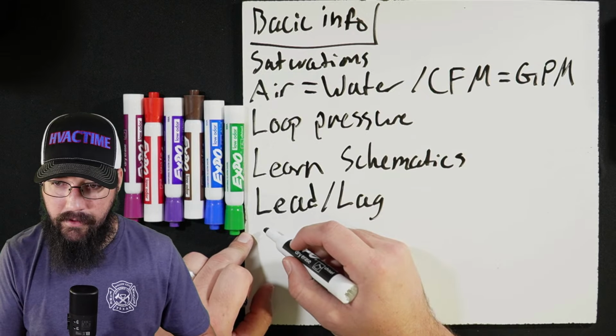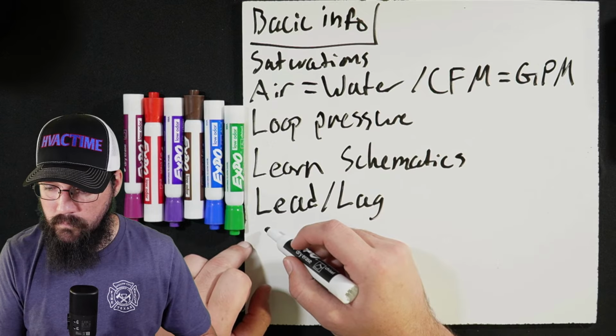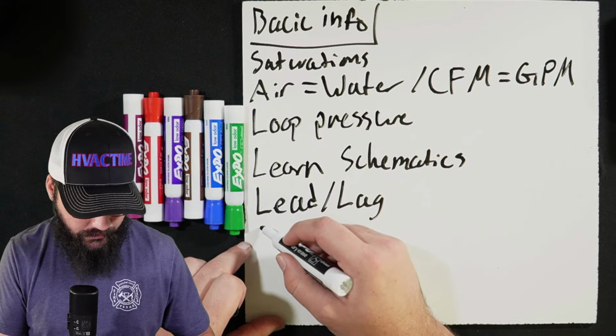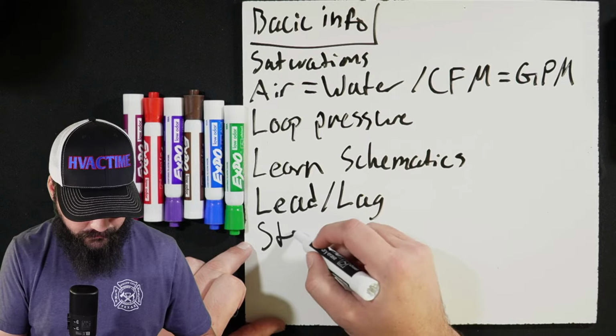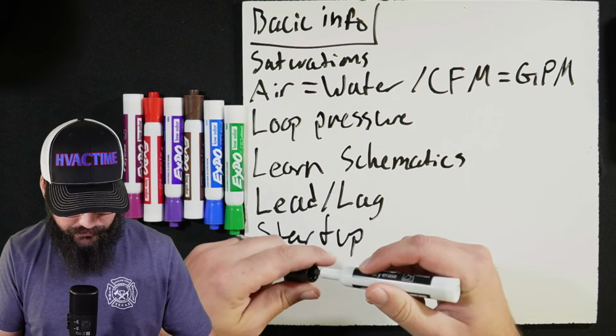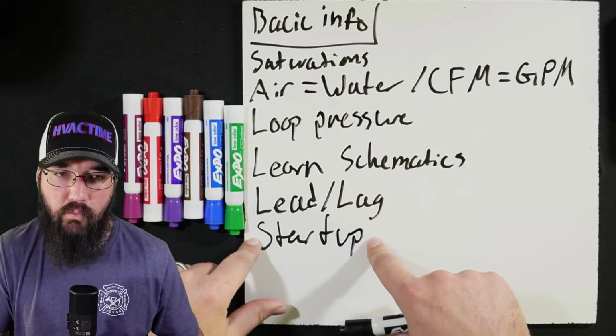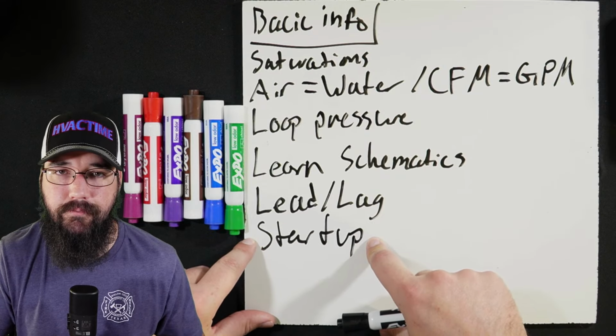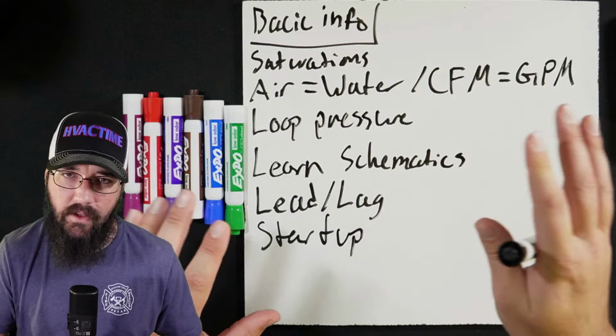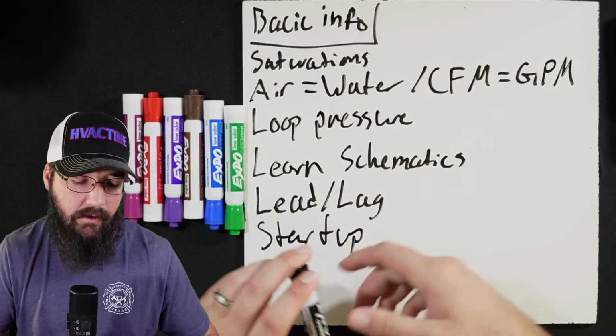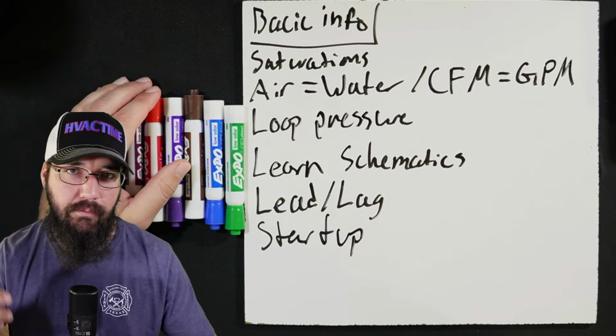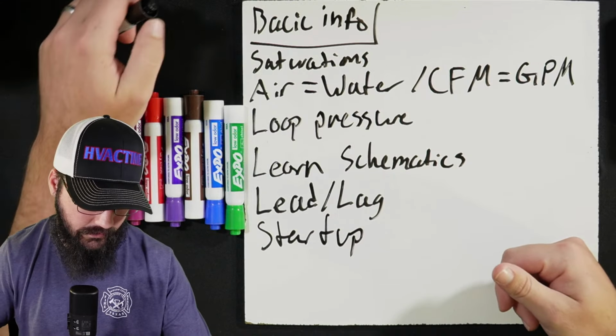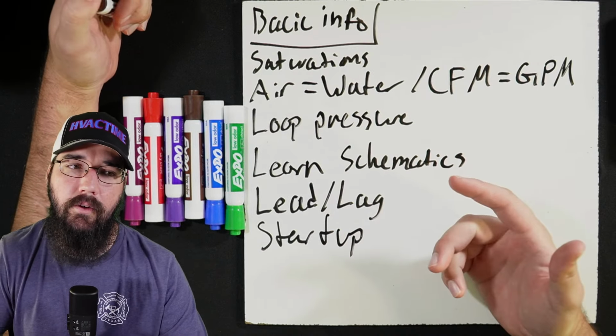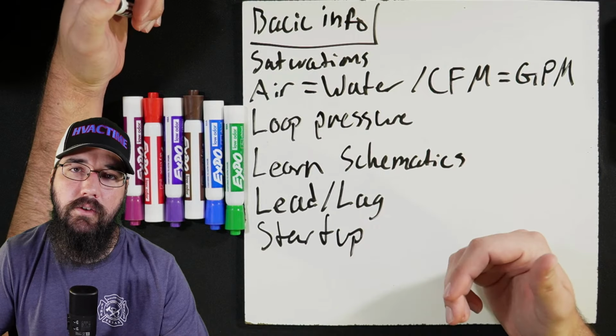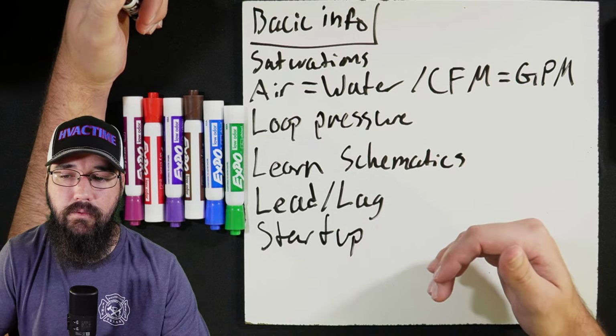And then really getting your head around the startup sequence. And what you'll find with an RTU, I know with split systems on a thermostat, once it turns on cooling, fan, compressor, everything kicks on basically simultaneously. With an RTU though, what's the first step of that process when it gets a command to turn on?